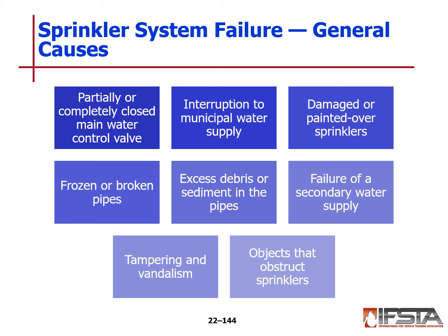Frozen or broken pipes, probably one of the most common ones that we encounter and see. We get this in the wintertime. You'll get a deep freeze. Temperatures will be well below freezing, even near zero. And it's when the warm up occurs that you start getting the alarms, because when it freezes, it will bust the pipe or a component in the system. Then when it warms up, everything begins to thaw out and leak, and cause water flow. This is when you'll get the alarm for it. Excess debris or sediment in pipes from the water system can cause problems. Failure of the secondary water supply, pumps, fire pumps, and things like that.